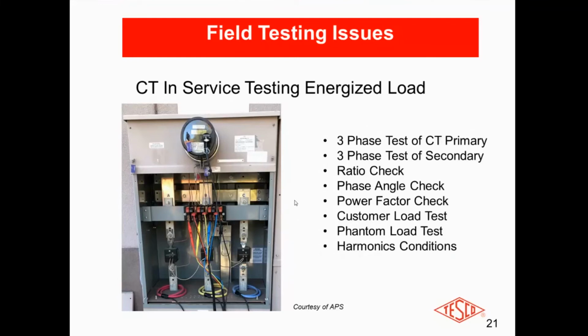Underneath there, you can see each of the A, B, and C phases with a double wrap on the cables, which allows us to get at least twice the amount of current in a low current or low load situation. So here we're gathering all the information required: three-phase test of the primary, three-phase of the secondary, ratio, phase angles, power factors, and we can do tests under customer load conditions or phantom load conditions, which is also very common - full load, light load, power factor test, and include harmonics and a whole range of other things.